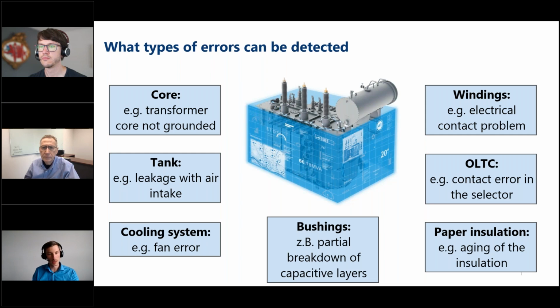Of course there are more, but just to show an example: we can have problems with the tank, there can be leakage, there can be air intake. We can have problems with the cooling system, the fan can be blocked, so there's a fan error. We can have problems with the bushings, for example a partial breakdown of the capacitive layers. We can have problems with the windings, like you saw earlier on. We can have problems with the on-load tap changer, and of course also with the paper insulation.